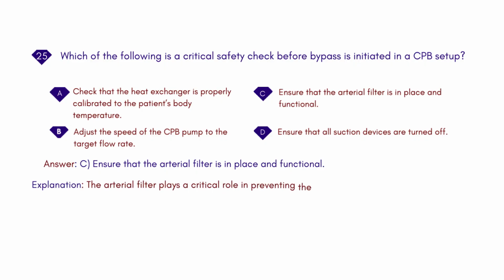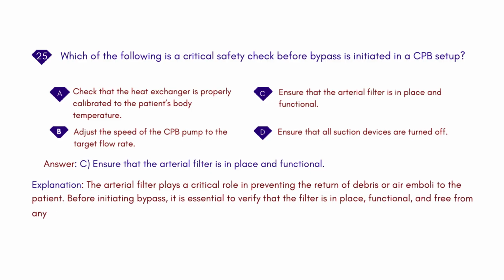Explanation: The arterial filter plays a critical role in preventing the return of debris or air emboli to the patient. Before initiating bypass, it is essential to verify that the filter is in place, functional, and free from any blockages.